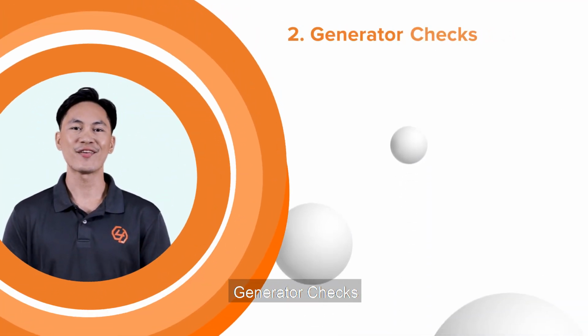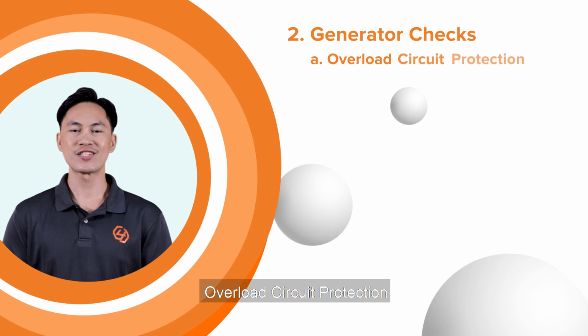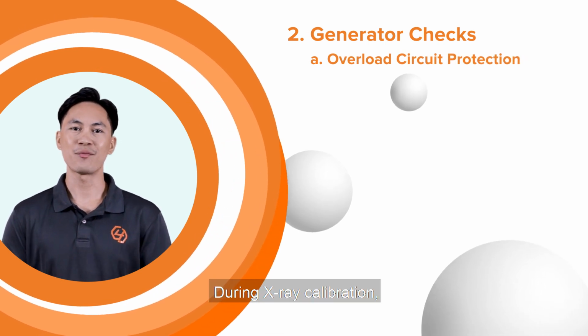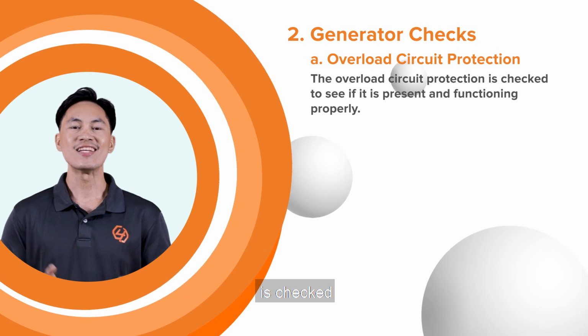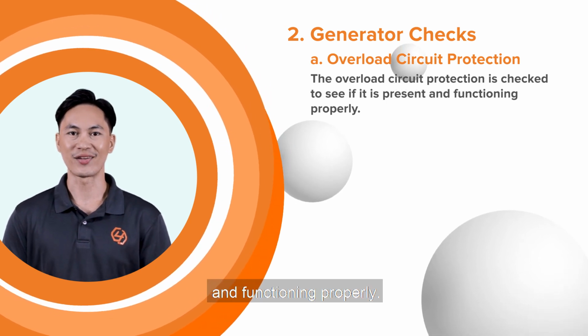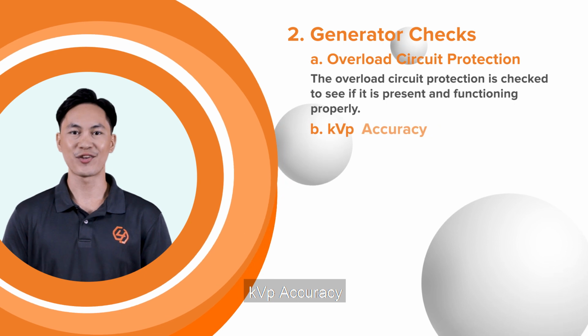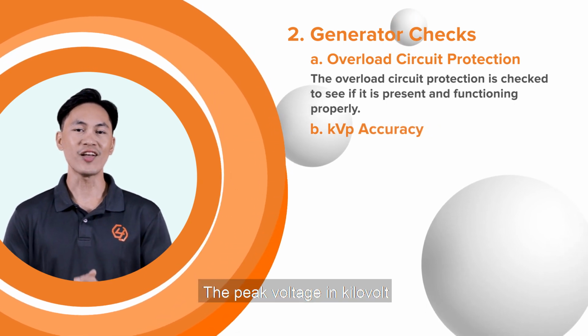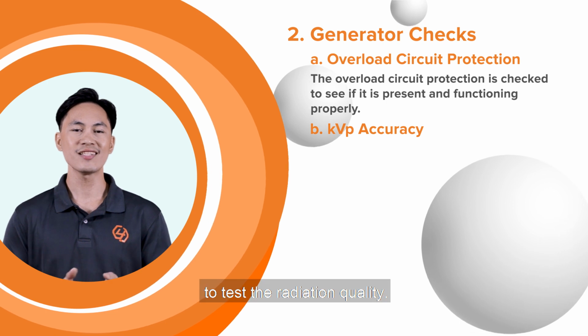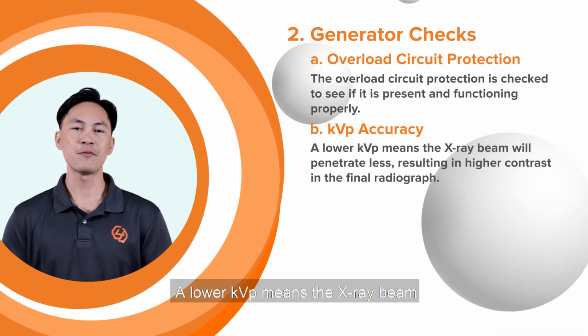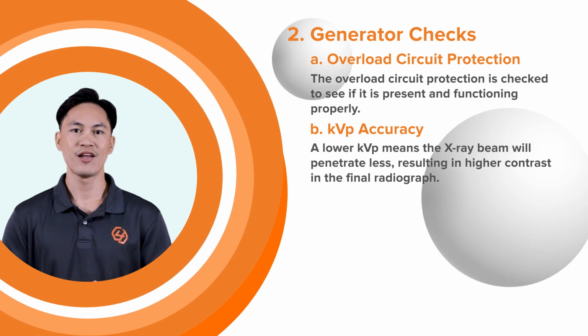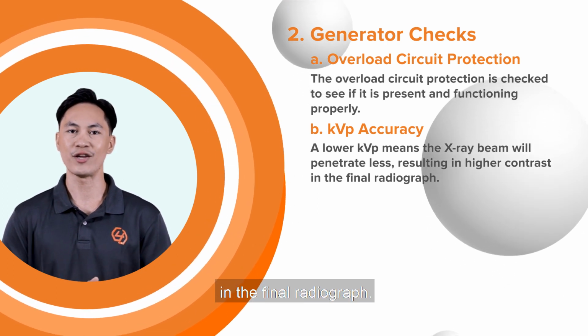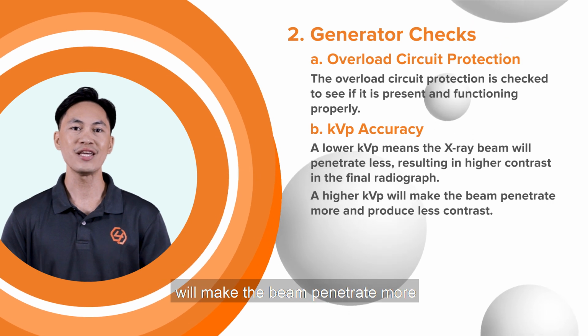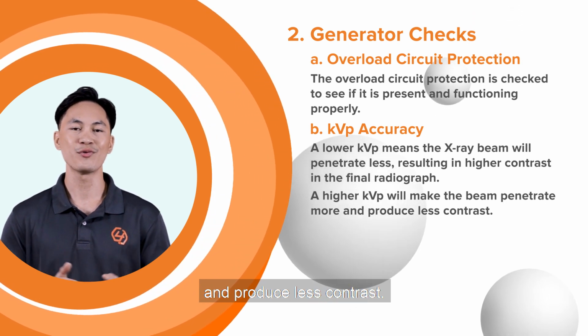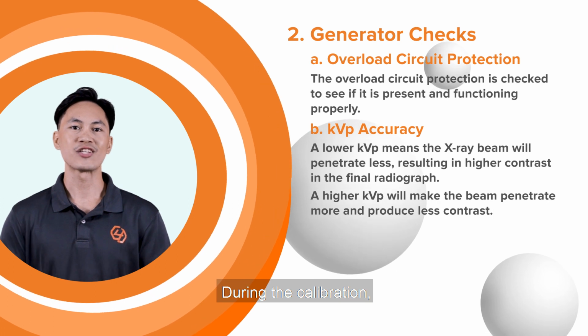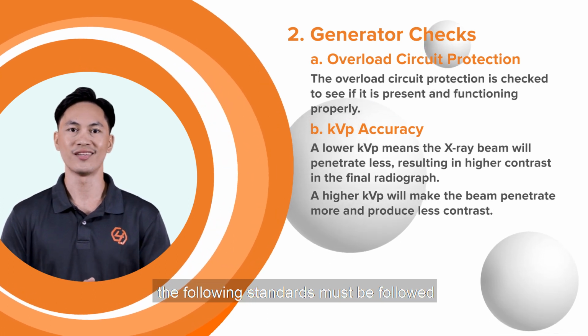Number 2. Generator checks. A. Overload circuit protection. During X-ray calibration, the overload circuit protection is checked to see if it's present and functioning properly. B. kVp accuracy. The peak voltage in kilovolt or kVp is checked to test the radiation quality. A lower kVp means the X-ray beam will penetrate less, resulting in higher contrast in the final radiograph. Meanwhile, a higher kVp will make the beam penetrate more and produce less contrast. During the calibration, the following standards must be followed.